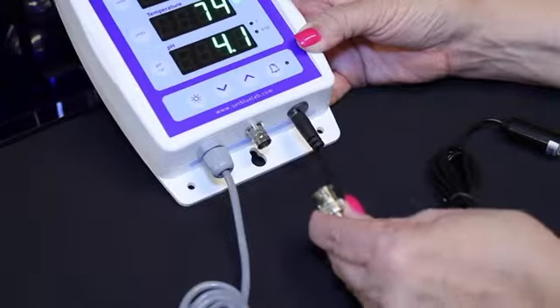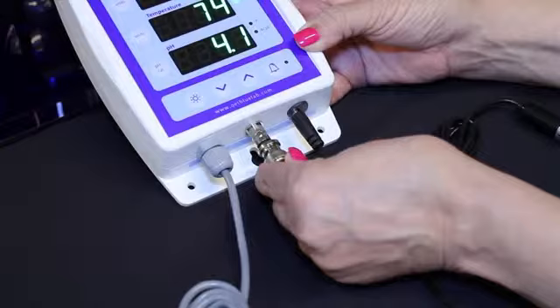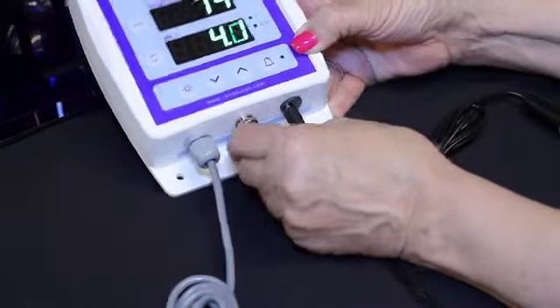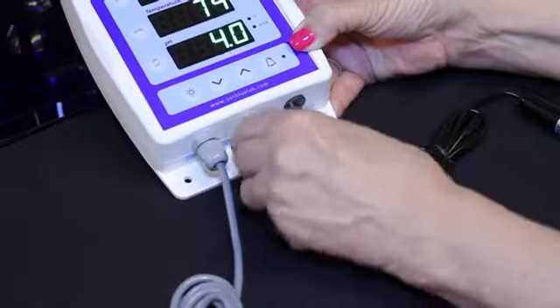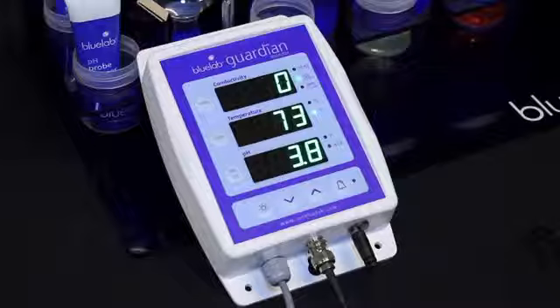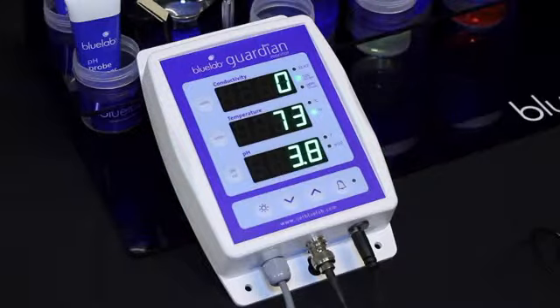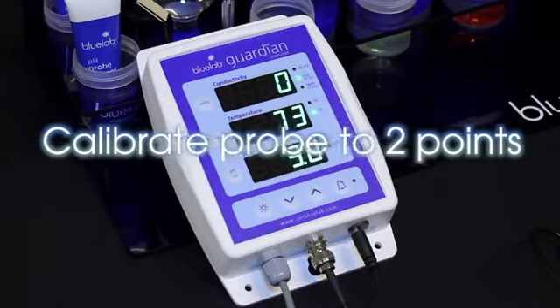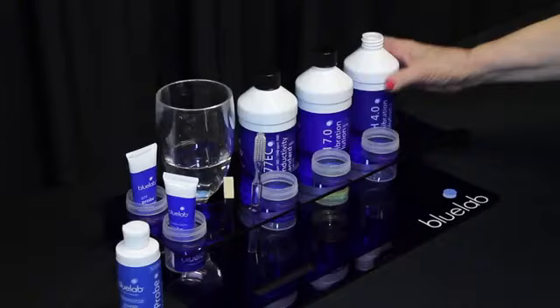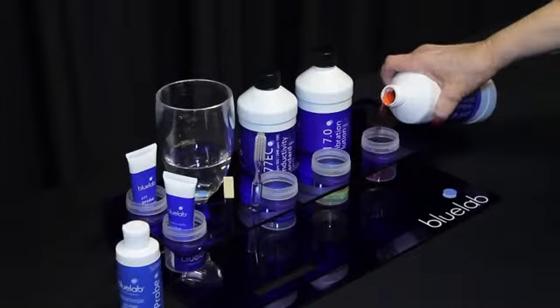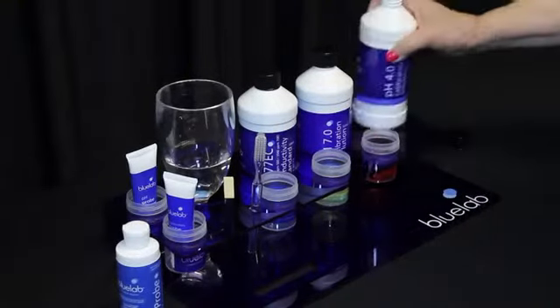Connect the pH probe to the Guardian monitor by lining up the lugs of the BNC fittings. Fasten securely by pushing the pH probe connector on and twisting 1/4 turn. The pH probe needs to be calibrated to the monitor before you take readings. Calibrate your pH probe to 2 points for accuracy. Use freshly poured pH 7.0 and pH 4.0 calibration solutions.